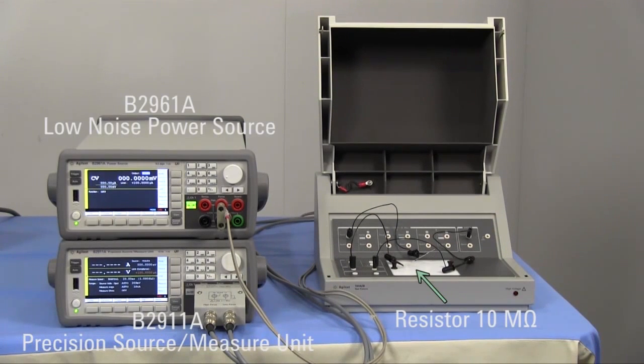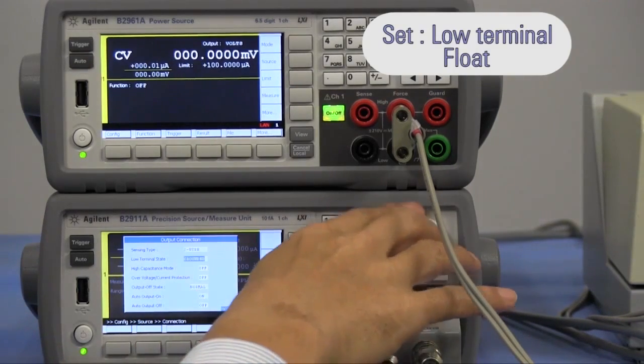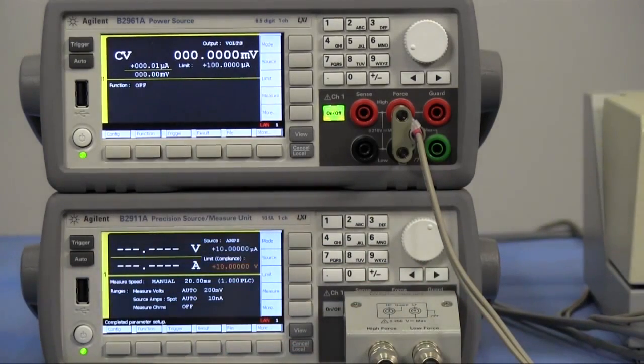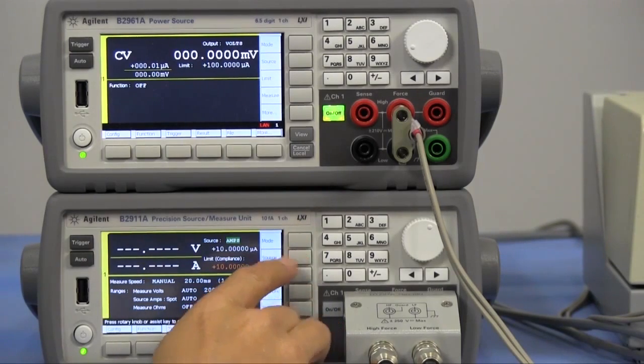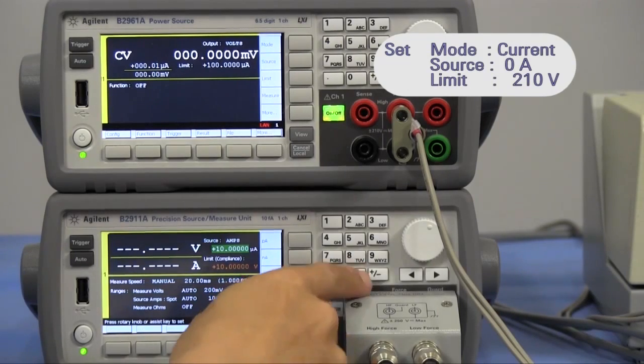This is the actual setup. Let's set up the SMU which works as a voltmeter. This SMU can be set to floating. So I'll set the low terminal setting to floating. Next, I'll set the mode to current force mode and then source value to 0 amp.